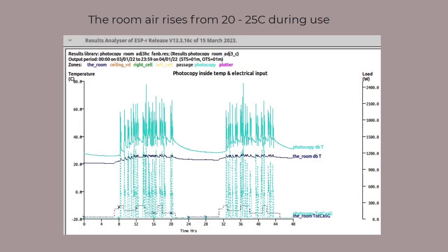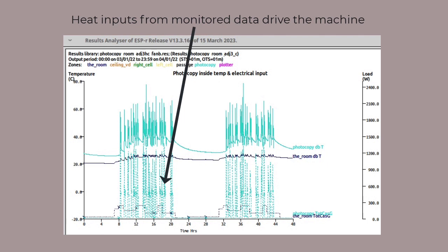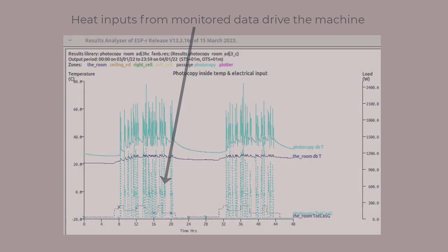If we plot temperatures in the room and in the machine, along with heat injections into the machine, we see that the room temperature rises roughly 6 degrees during the day, falls back a bit at night. The machine temperature is all over the place. If we guessed 50 degrees C as an average, well, a stopped clock is correct 2 times a day.